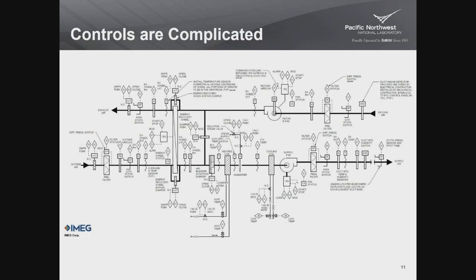And this slide is just to show you the level of complication. This is the submittal from a mechanical engineer for an air handler. In some ways a little bit similar to the screenshot you saw before, but showing many more points of control: temperature sensors, coils, filters, fans. And this is just for one single air handler in a building. In a large building, there could be 20, 30 or more of these. There are similar control schematics for pumps, fans, chillers, boilers. So there's a lot of complexity involved in building controls.